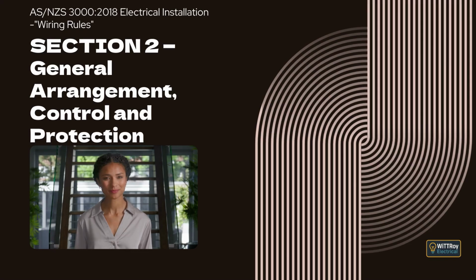Clause 2.6.3.3.4, Additions and alterations, New Zealand only. When circuit protection on an existing switchboard is replaced, additional RCD protection must be added to the final subcircuit supplied from that switchboard. If socket outlets are added to an existing circuit, and RCD protection is required, the RCD should ideally be installed at the start of the subcircuit, but it may also be installed at the beginning of the new wiring only. Any new RCDs must be recorded at the switchboard.